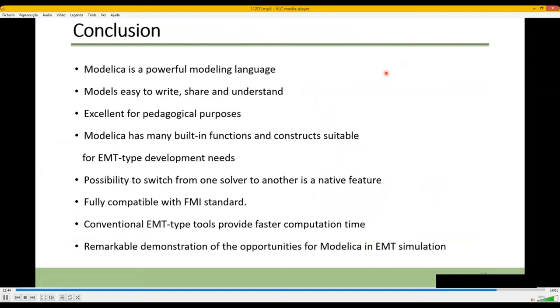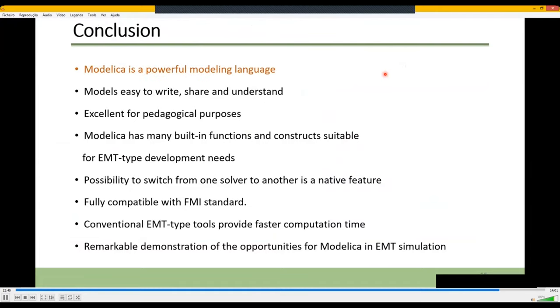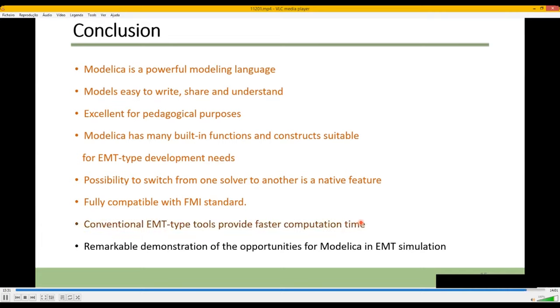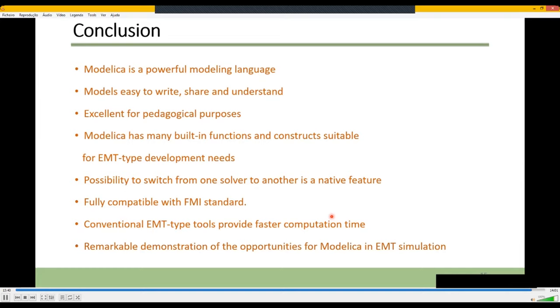Let's conclude the presentation. Modelica is a powerful language for EMT simulation. The two major electrical elements — the wideband and constant parameter models — are demonstrated here. Modelica models are easily readable and understandable, which is important for pedagogical purposes. Built-in operators such as derivative and delay make modeling easier. Since the model is decoupled from the solver, it's possible to switch from one solver to another. Modelica is compatible with FMI, allowing co-simulation and model exchange, with the number of supporting software increasing. The computation time is not yet comparable with EMT-type tools, but the future is promising. We believe there is opportunity for Modelica EMT simulation of power systems.